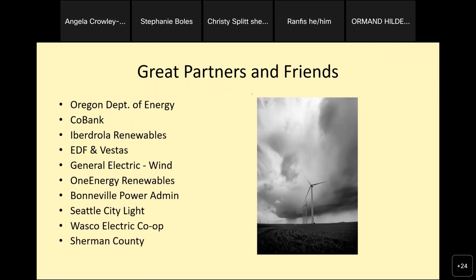Well, I have, and that's one of the areas I want to go down. As I mentioned, everything I have is built out for 10 megawatts, but I have a net capacity factor around 36%. That means 65% of the time my buildout, my below-ground distribution line, my substation, my transformer, my interconnection with Wasco Electric, my BPA transmission, is not being utilized to its fullest capacity. Why can't I put in 10 megawatts of solar with storage capacity on a battery that gives me maybe a 2-hour battery shift? Then all of a sudden my power becomes much more valuable to the grid.